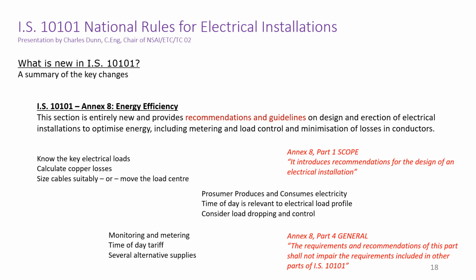So the energy efficiency section, as proposed as a part, is now only an annex, and comes with the advisory note that it introduces recommendations for the design of an electrical installation. Note that: recommendations, not rules. So Annex 8 content is not mandatory. In fact, the Annex 8 text goes on to advise that the requirements and recommendations of this part shall not impair the requirements included in other parts of IS 10101. So there is nothing in Annex 8 that is mandatory, and nothing in Annex 8 can overrule any other rule.